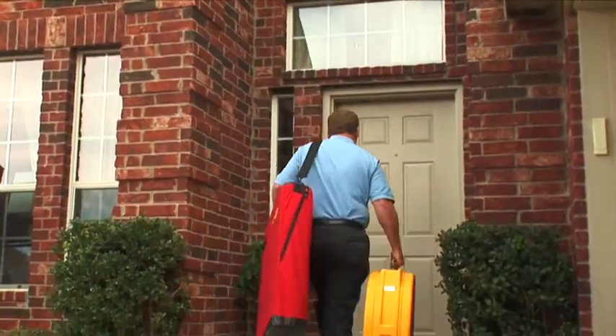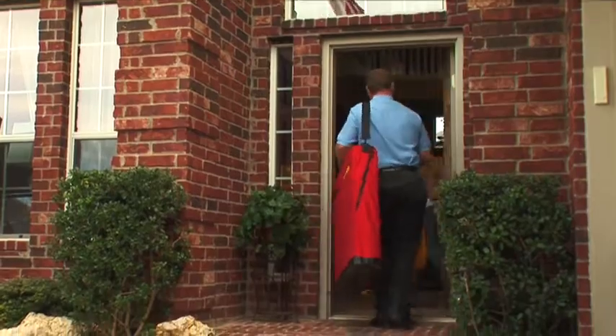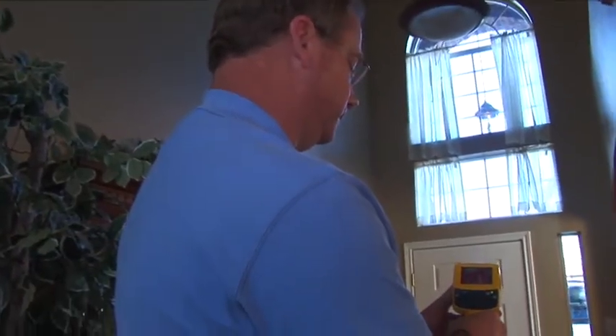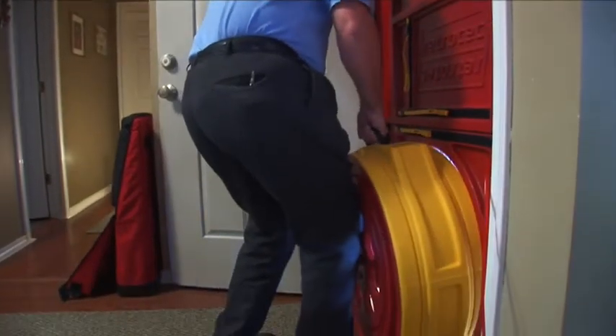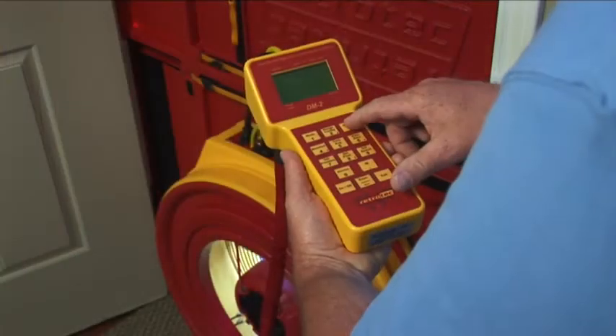The first step is to get a home and duct performance test. The process begins with a short interview of the adults living in the home. Next, your consultant will perform a series of inspections and tests. The primary test measures how leaky your home and ductwork are. This is done using a computerized diagnostic instrument called an infiltrometer blower door.